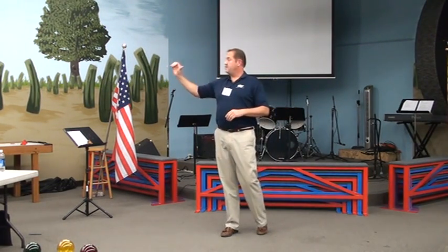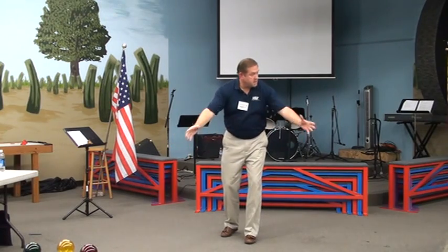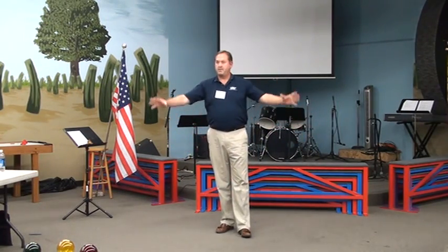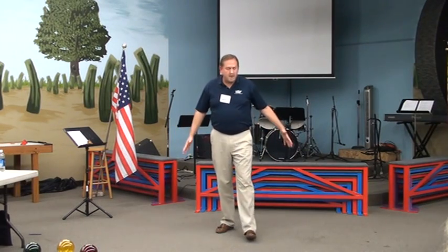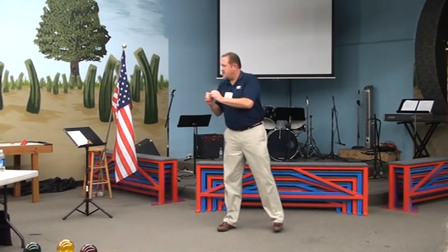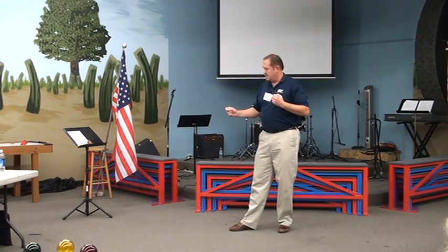If you have a current going this way, the magnetic field travels around that wire like this. So as we do a circle, you get a donut-shaped field, half out of the ground and half in the ground. When you drive up over that, all of a sudden it says, okay, there's someone there. It can tell because the current in the wire actually changes its speed. There are little detectors in the controller, and it says, oh, there's something there.